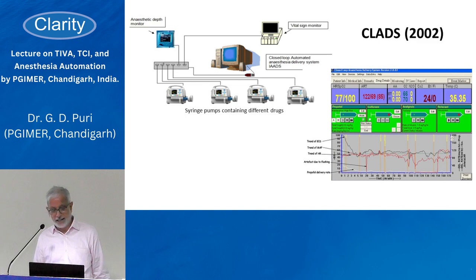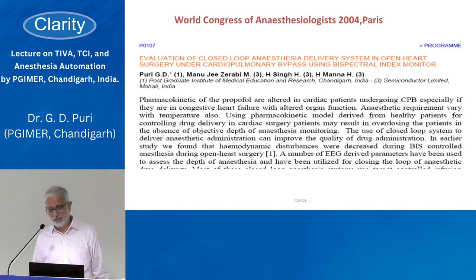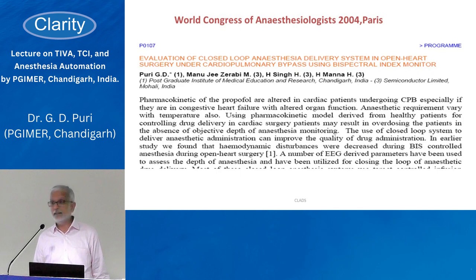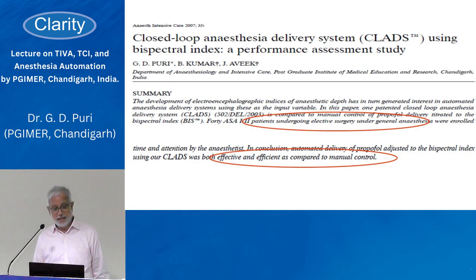We developed this system about two decades ago and initially presented it at the Paris World Anaesthesia Conference. Dr. Jatana, who was working at Semiconductors Limited, helped in initially making the system. The article I'm referring to had Dr. Bhupesh and Dr. Avik as co-authors. What we found was that closed-loop anesthesia is not only possible but effective and efficient compared to manual control — requiring less drug dosage and less BIS overshoot, since boluses are not given manually.